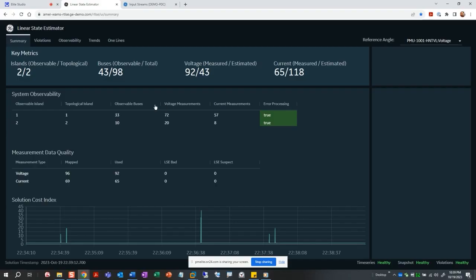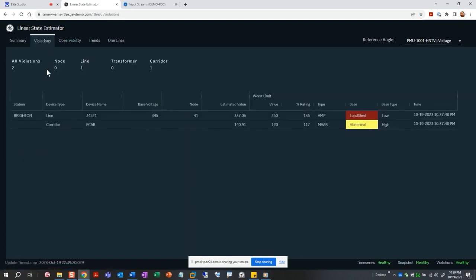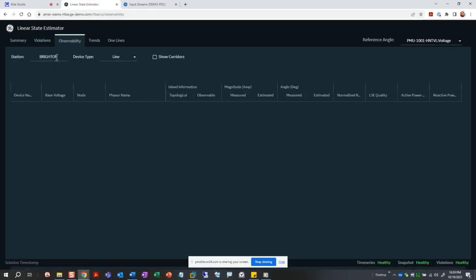So some additional information that you'd want to see as an operator or as somebody who's using a linear state estimator, you would want to see the violations on the system. So we just have 2 violations simulated here. So at Brighton, we've got a transmission line that's exceeding the amperage limit on its load shed rating. So we're at 135% of the 250 amp rating on this transmission line. The corridor is a tie line, so it's a transmission line that ties to your neighboring system. We've set a megavar limit, so it's in an abnormal state. So that megavar loading on that transmission line is very high and abnormal, so it's something we'd want to bring to the operator's attention.